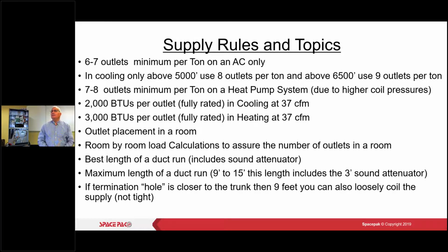Let me see, if we're doing 7 to 8 outlets minimum per ton on a heat pump system. All right, so again, 7 seems to be that number. Again, 2,000 BTUs on the cooling side, 3,000 BTUs on the heating side. And again, that's if we're moving 37 CFM. The longer you make those runs, the less CFM you're going to be able to deliver, and then the more outlets you're going to need per room. So we need to do those calculations.